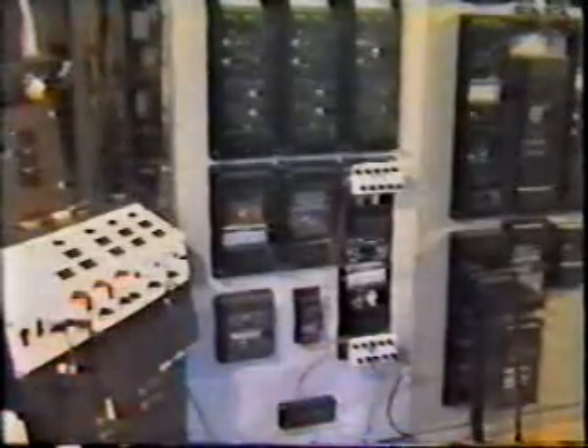Before leaving the manufacturer's works, it is to be expected that each relay will have been thoroughly tested to see that it meets specification. However, it is still necessary to perform functional tests on site with the relay in its installed location, and also to calibrate the relay for this particular installation. The necessary calculations and written instructions are issued by the power company's protection department.